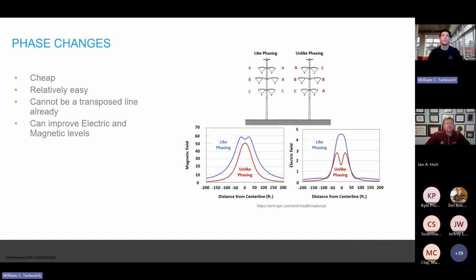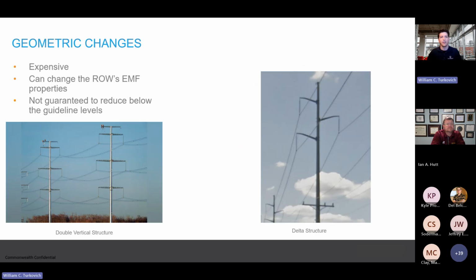And all you're doing is just changing the different conductors. The only catch with changing the phases is, back to the beginning, what if this is a transposed line? What if this is ABC down on both conductors, but then a third of the way down it changes to ACB or CBA? Then a third of your line is always above your limits. That doesn't help you.